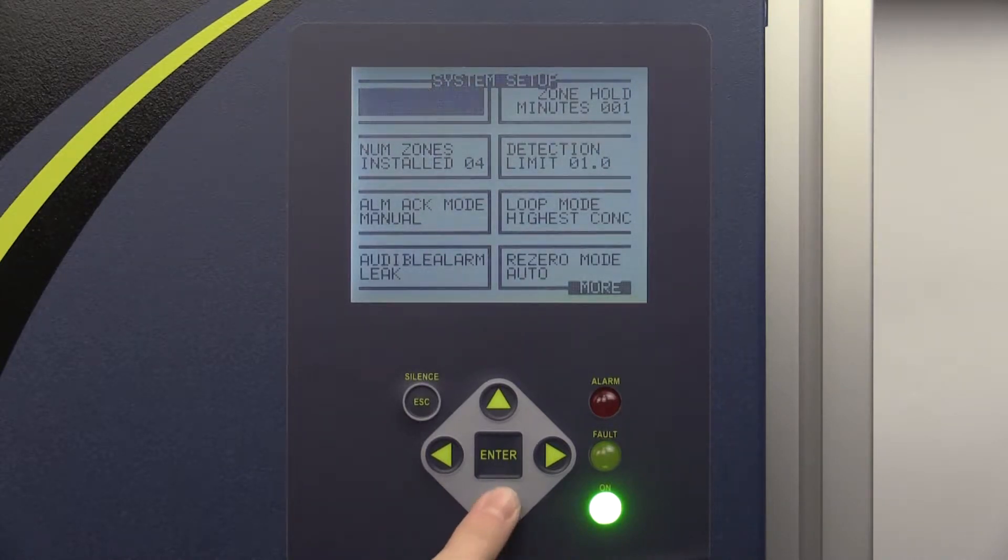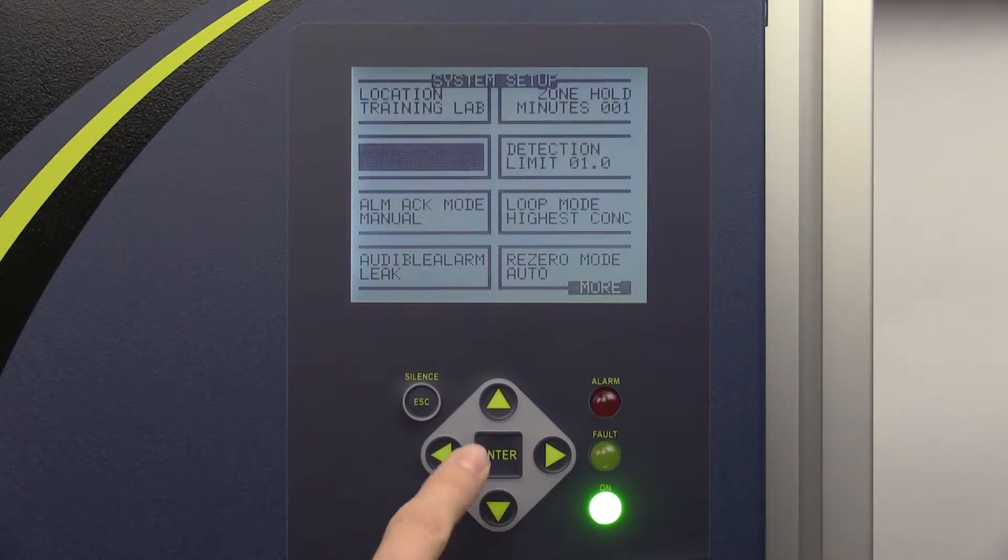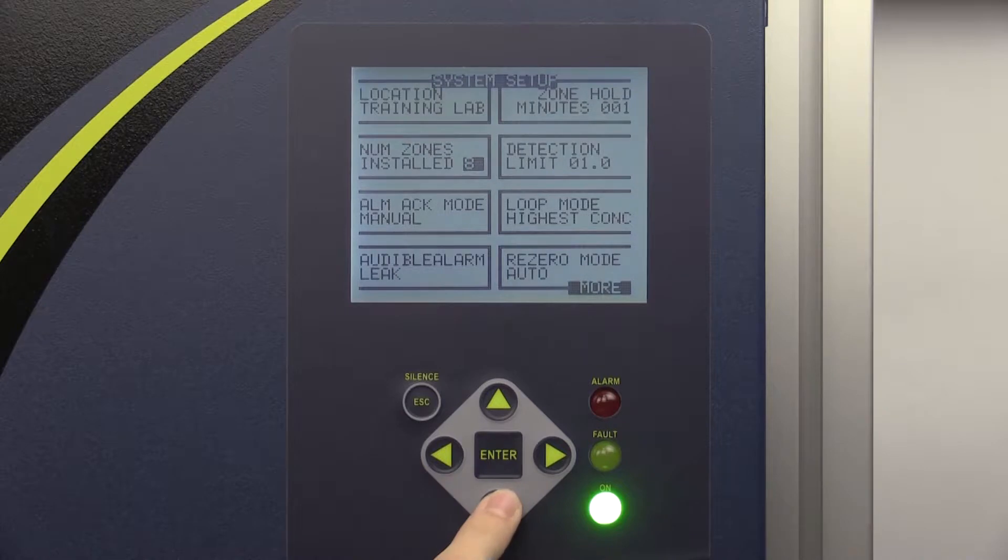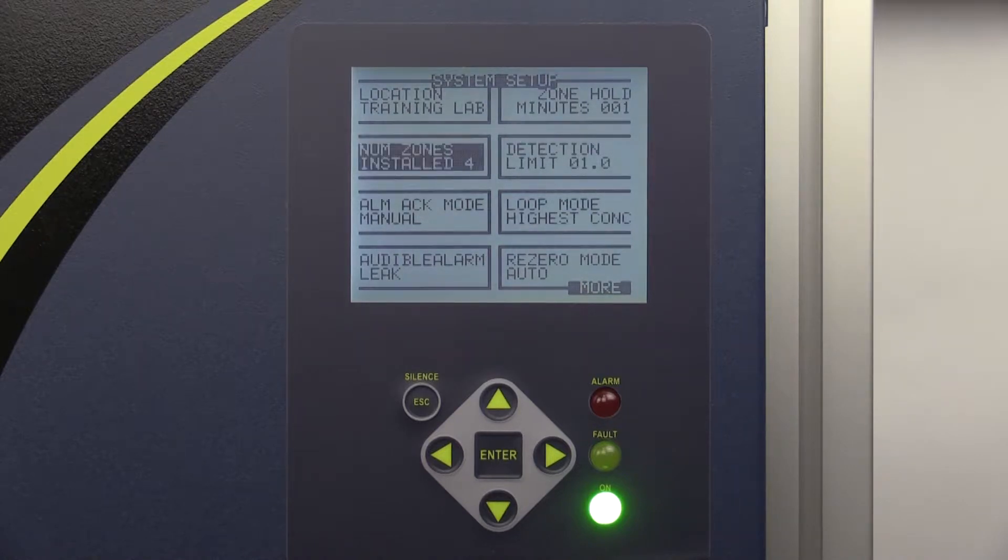The number of zones installed tab should indicate the number of manifolds connected to the side of the monitor. This number can be changed by highlighting the number of zones installed tab, pressing enter and using the up and down arrows to edit the number. If the number of manifolds you have installed is not a multiple of 4, round up to the nearest multiple of 4 and enter this number into the box. We can correct for any unused ports later when setting the length of tubing for each port on the zone setup screen.